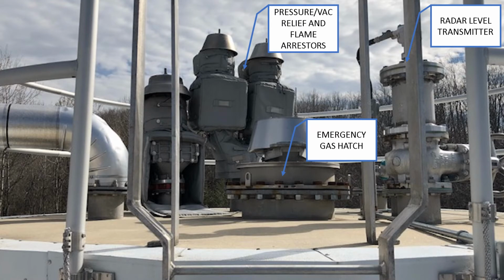There are a handful of devices on top of each digester. There are a series of pressure and vacuum reliefs, really intended to maintain the structural integrity of the tank if we were to ever build too much pressure or start to draw a vacuum. Each of those systems have flame arresters or flame checks in line, so if a flame was to ever develop, it would prevent it from traveling further down the pipe and causing a larger fire or explosion.